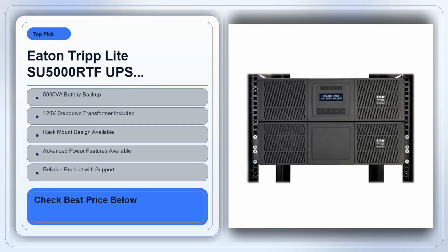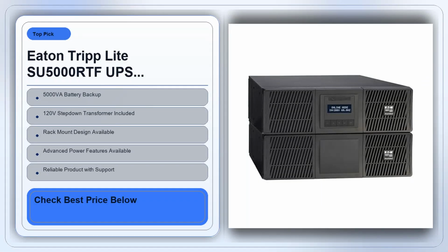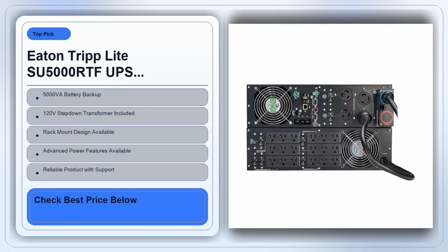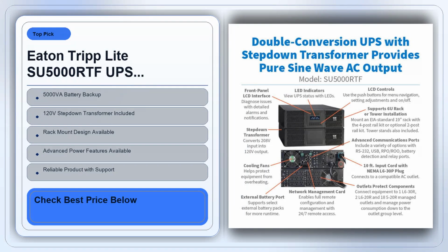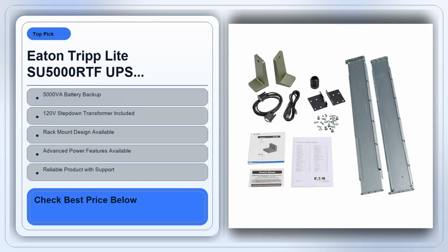The core of the unit is an online double conversion topology. Unlike line interactive models that ride the wave of the incoming power and only kick in when there's a serious dip, the double conversion design continuously converts incoming AC to DC and back to AC. The practical payoff shows up the moment the lights flicker during a storm. Your servers stay on a perfectly clean sine wave, no hiccups, no reboot cycles.